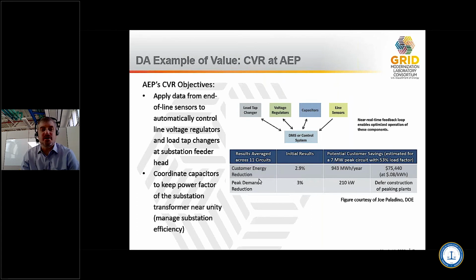From a customer energy reduction standpoint, this is a completely automatic system. It's active, reading those end-of-line sensors, making a decision, and changing the load tap changer, voltage regulator, and capacitor settings, not second by second, but on a relatively fast basis, probably something like every 15 minutes.